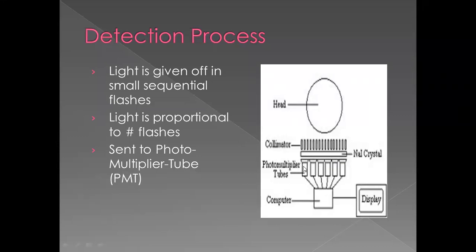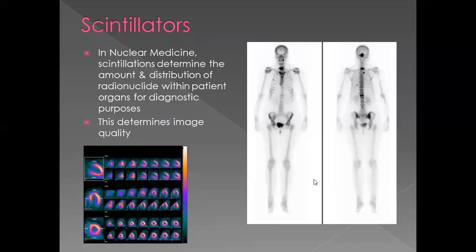The PMT tubes transfer photons to electrons and then to electrical pulses, which are sent to the computer to display the image. The light given off from the crystal is in small sequential flashes, and the signal is proportional to the number of flashes. Whatever number of photons comes from the source or patient is faithfully captured by the crystal and sent on to the PMT tube. Two of the most common scans in nuclear medicine are cardiac and bone scans, and you can see here that we get great resolution and great images.